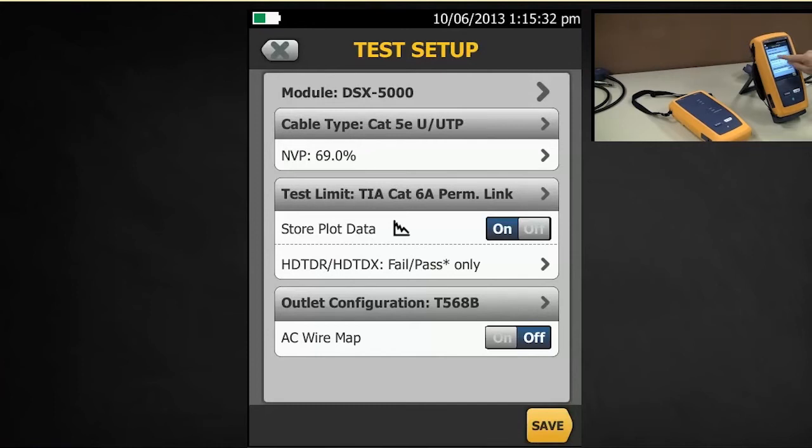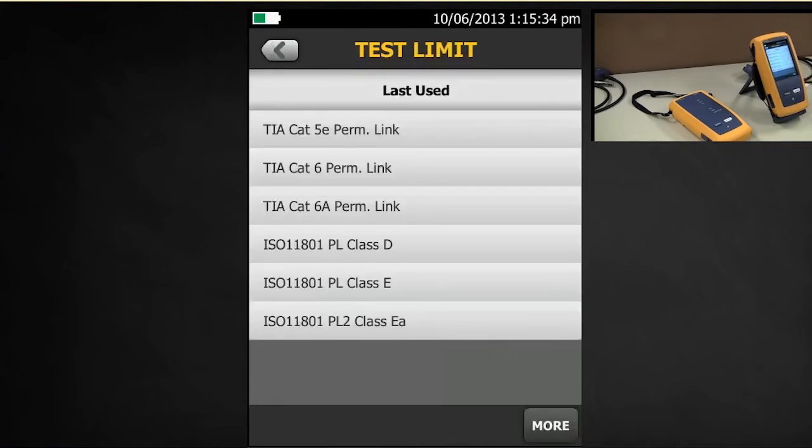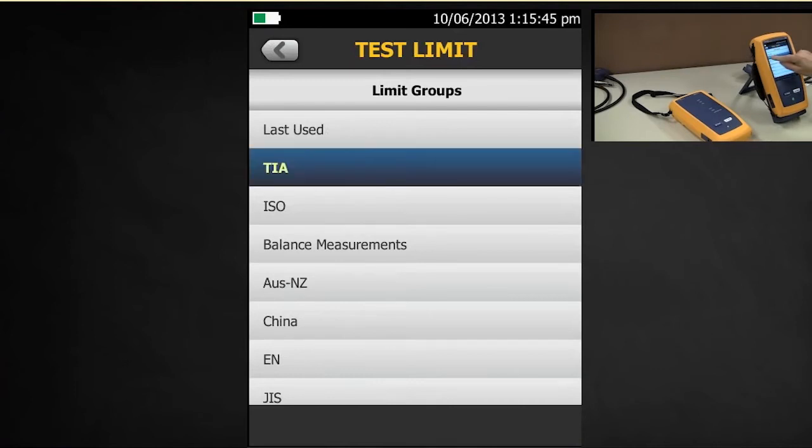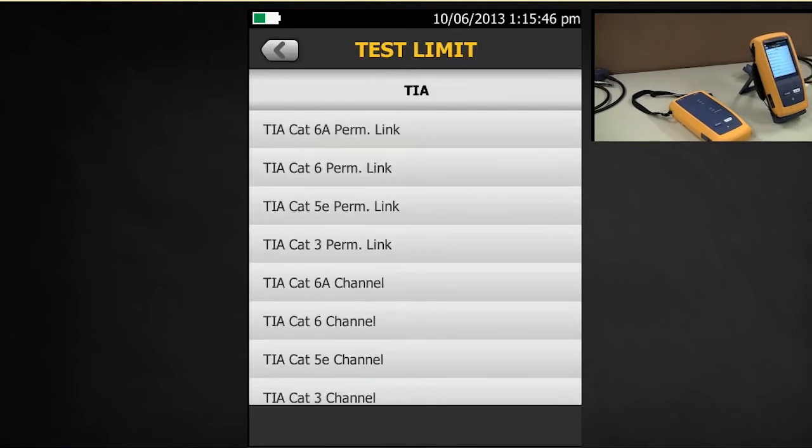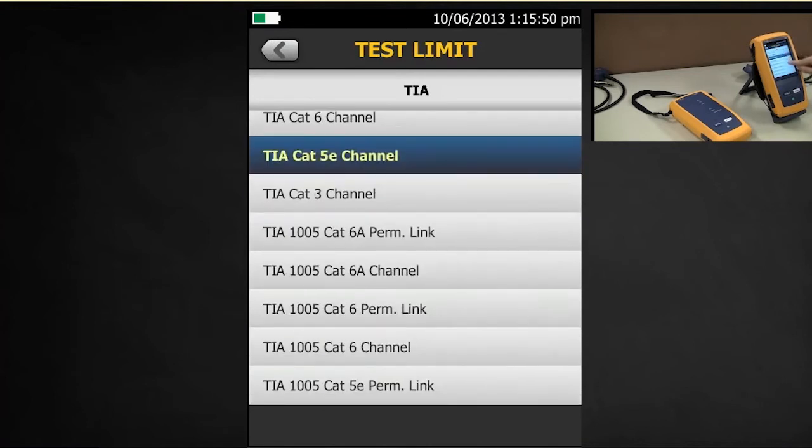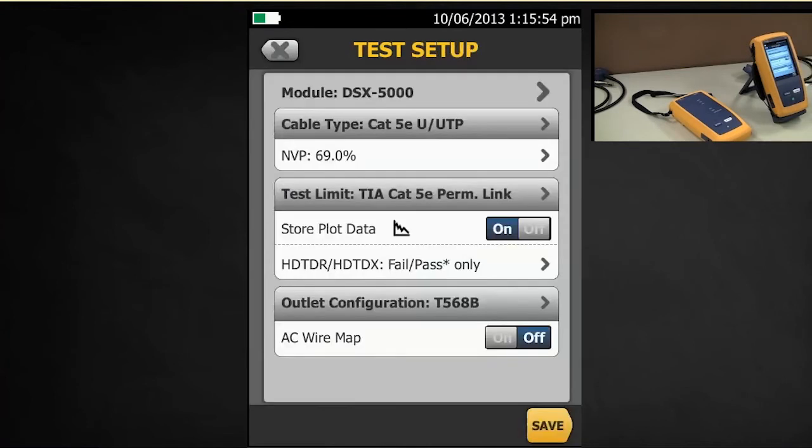Now I'm going to change my test limit. I'm going to select TIA Cat5e Permanent Link. This is the last used. If I tapped more, you can see all the various standards that are available to you. In fact, if I go to TIA, we see our list. Permanent Link first and then Channel underneath. So let's select Cat5e Permanent Link.